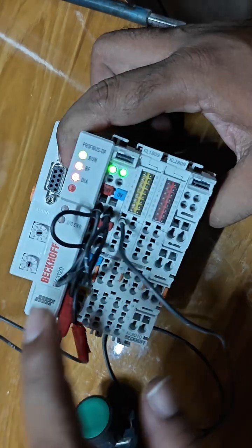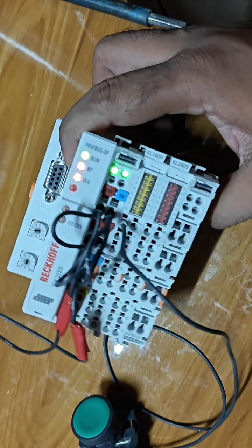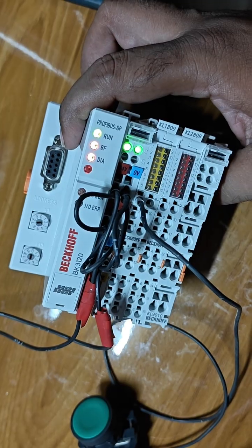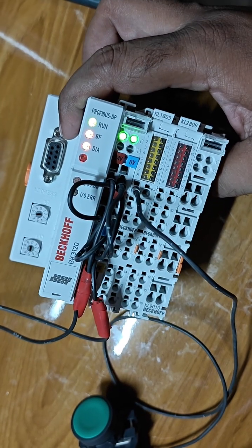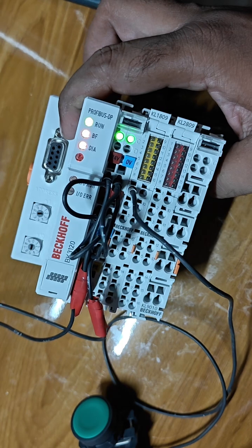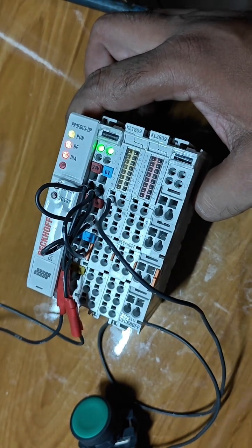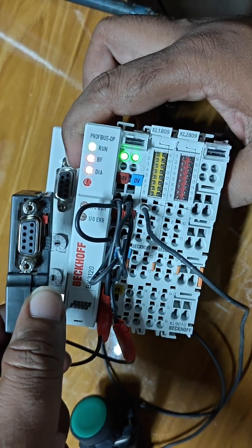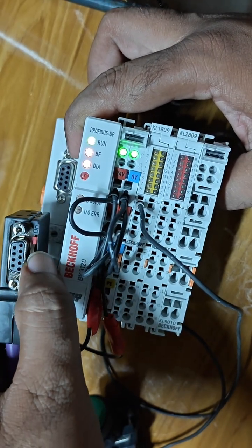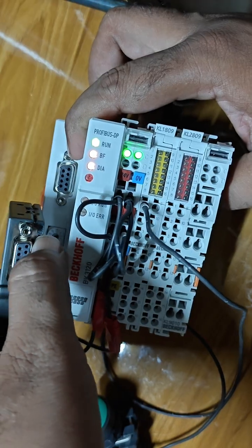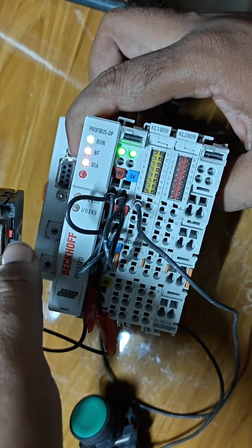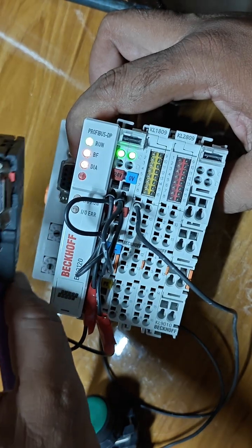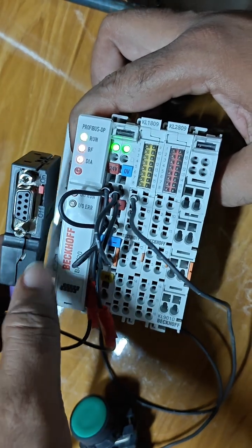After we connect this cable here, the Profibus status changes. Right now there is no communication, so bus fault and other indications are active: IO error, IO run. This is my Profibus cable and the termination resistance is in the on condition. On both sides the resistance is on. Now off and now on. This is the end of my Profibus cable, with no extension, so the resistance is on.